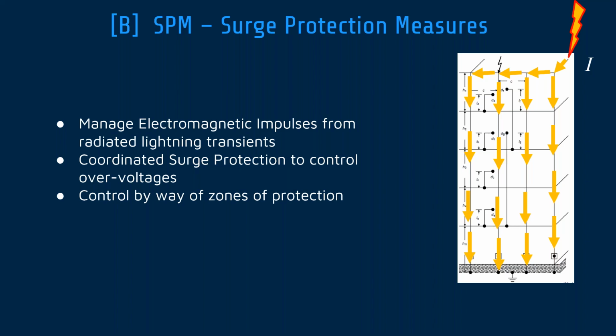So we need to manage electromagnetic impulses from radiated lightning transients. We try and implement a coordinated surge protection to control our overvoltages, and we do control it by way of creating zones of protection. So in a multi-story building where a bank has a very expensive server room, that would be the highest zone of protection. And like our power utility system, where the transformer has got multiple levels of surge arresters protecting it, the same goes for that kind of practice. But the documentation falls well short. And as a result, in our SANS 10142-1, our wiring code, there is conflict as to how we need to be implementing this and going forward with it.